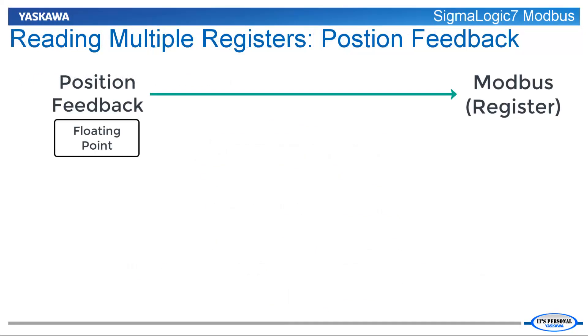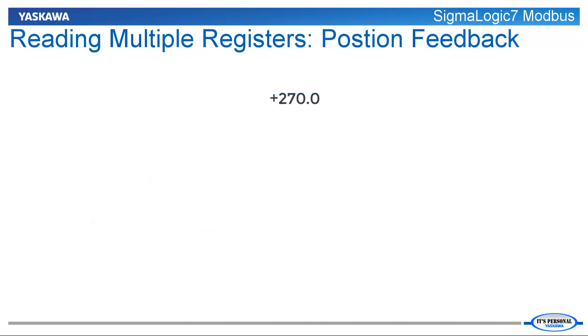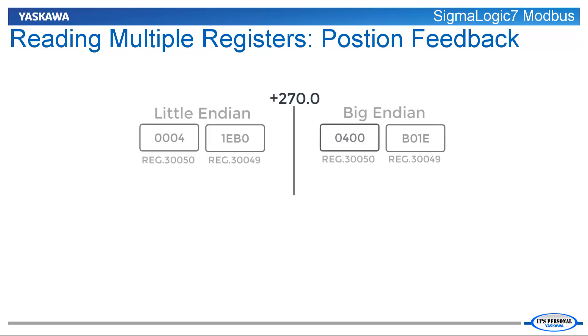Here is an example of reading the position feedback from the Sigma Logic 7 Modbus node. The node will automatically convert the floating point number to an integer of desired implied decimal places and place the data into a low and high word as 16-bit integers. For example, if the Sigma Logic 7 Modbus node is reporting a position of plus 270 degrees to the host, the node will put the data into input registers 30049 and 30050.